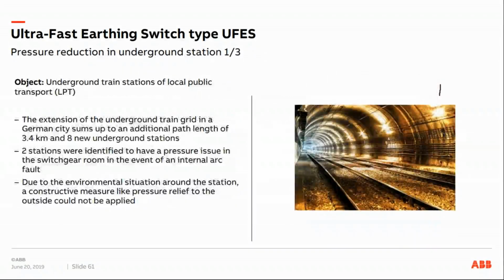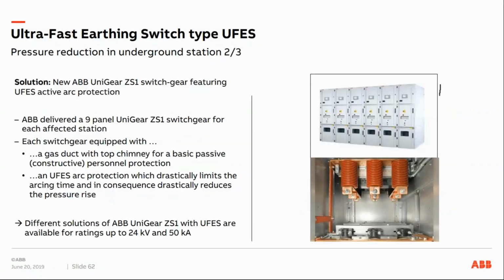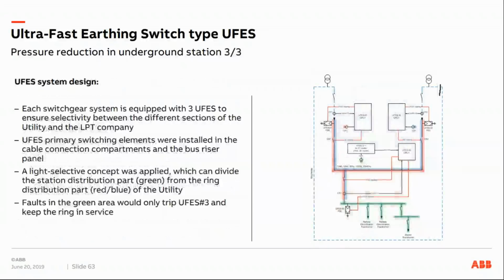Another option is a local public transport. Here again, the customer did not have much space to install any kind of pressure relief duct. So we've been retrofitting or providing, after an arc fault incident, new ABB Unigear panels equipped with a cable compartment equipped with the UFES primary switching elements. And that one was actually a more complex system. But here again, we can work on different selective solutions based on customer request.